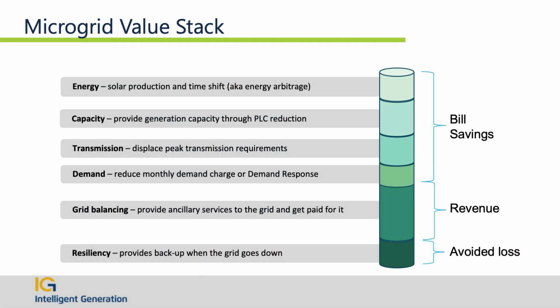Another big thing is demand. For those familiar with utility billing, a commercial customer is billed for two things: the energy you're using, and how fast you're using it, which is the demand charge, the KW. Kilowatt hours are like the odometer in your car, while the capacity or demand, those KWs, is how fast you're using it at peak.